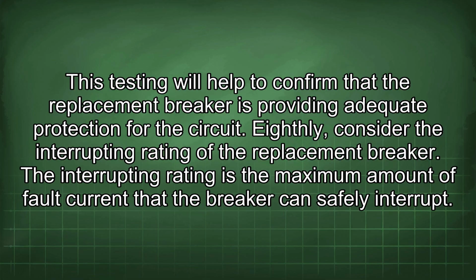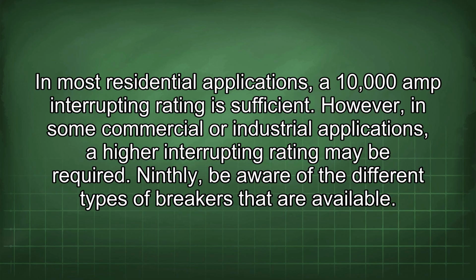Eighthly, consider the interrupting rating of the replacement breaker. The interrupting rating is the maximum amount of fault current that the breaker can safely interrupt. In most residential applications, a 10,000 amp interrupting rating is sufficient. However, in some commercial or industrial applications, a higher interrupting rating may be required.